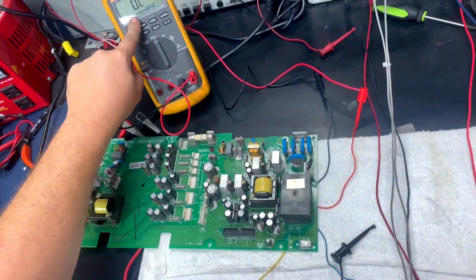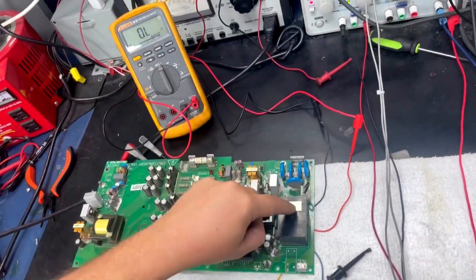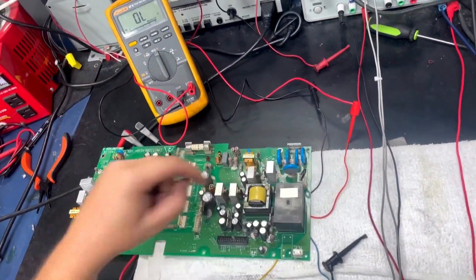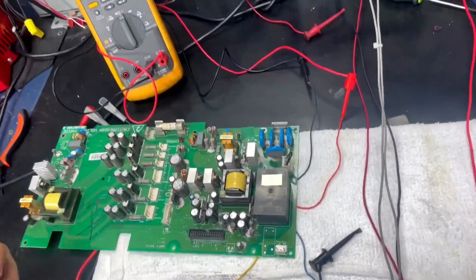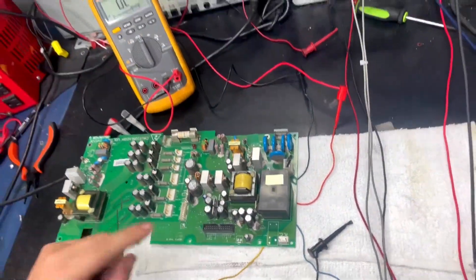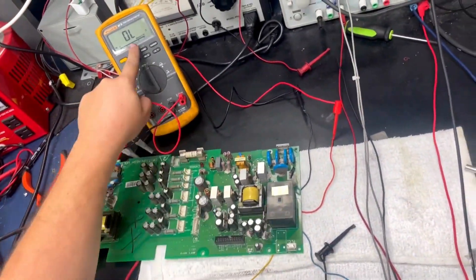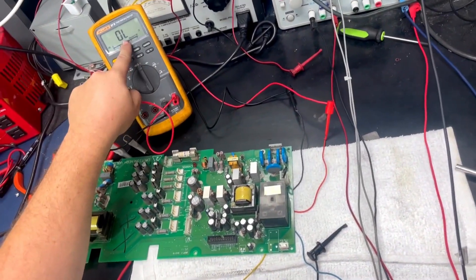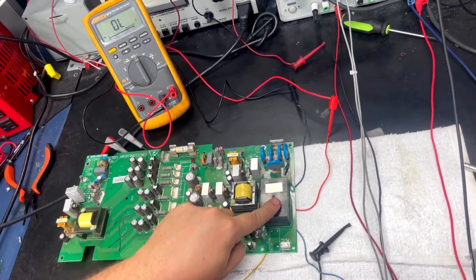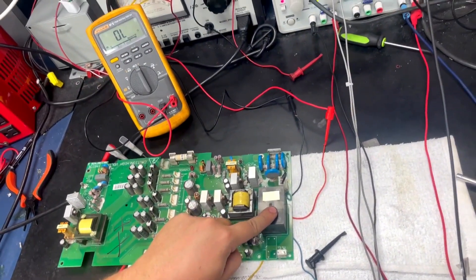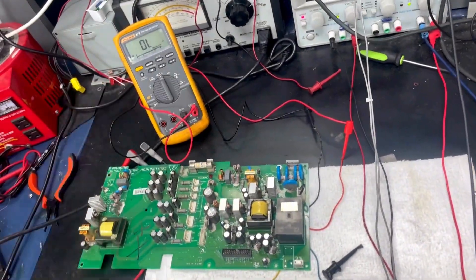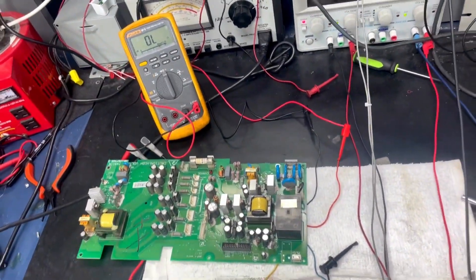This is a normally open relay, which means when there is no power, this is normally open. So right here, this is good. If this is a normally open relay and this would show a short, we knew that the contacts were fused and this was a bad relay.